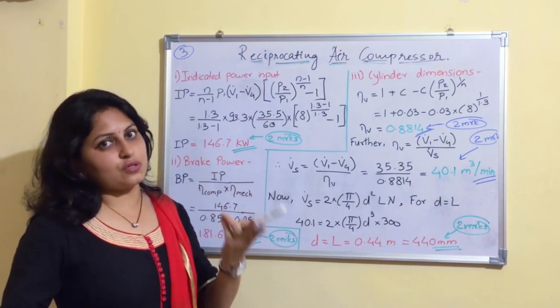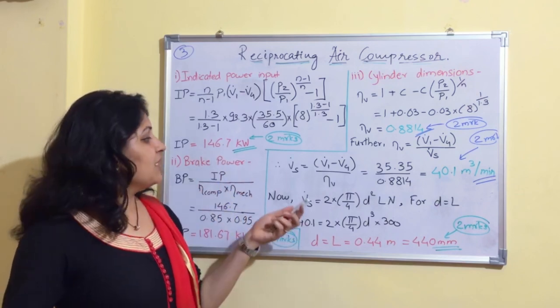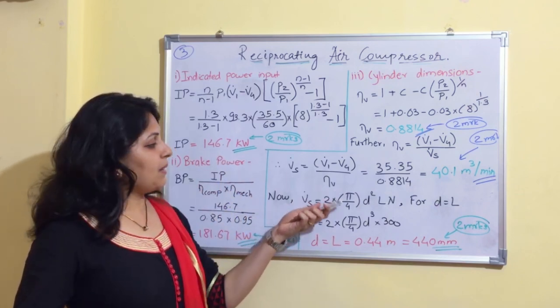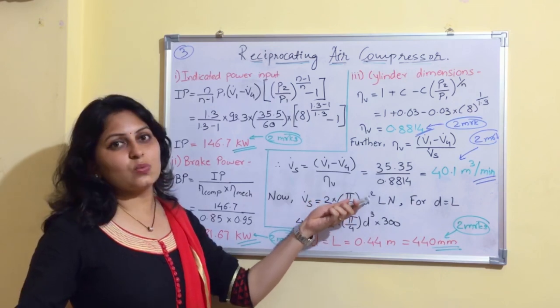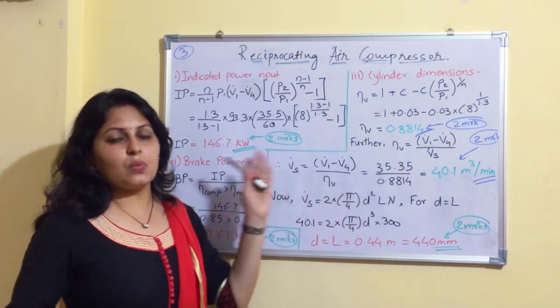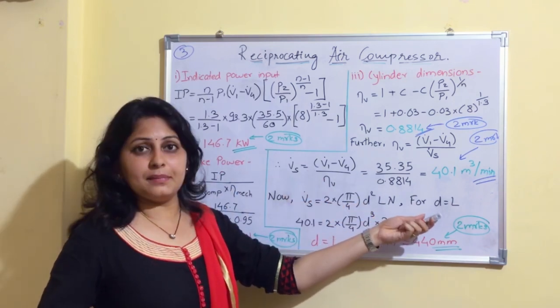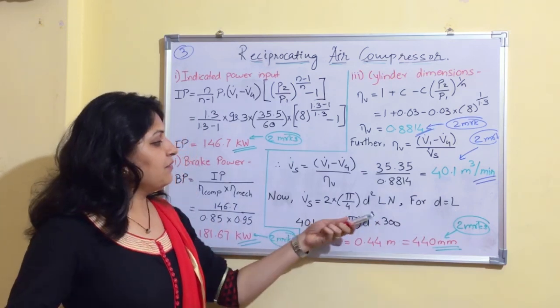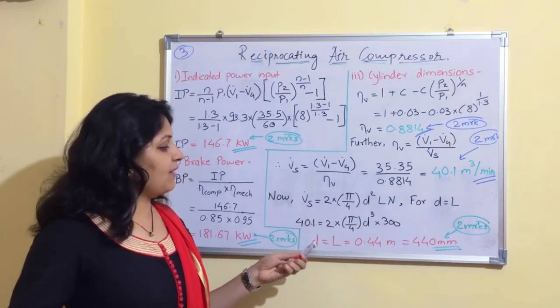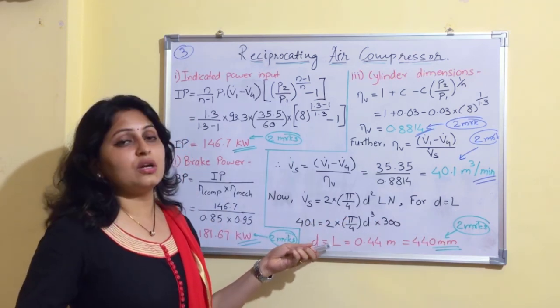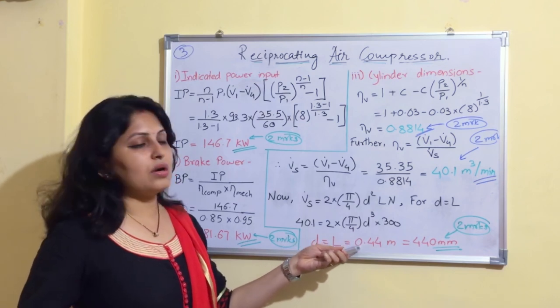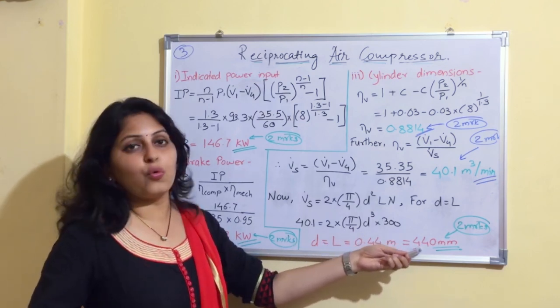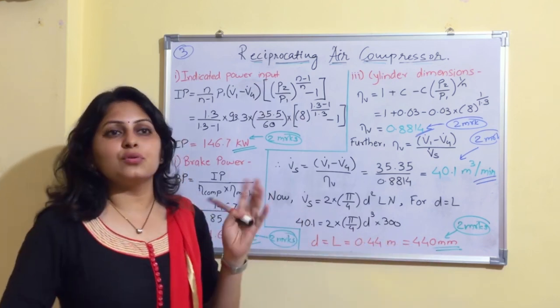Since there are two cylinders for single stage, the swept volume formula is Vs = 2 · (π/4) · D² · L · N. As given in the problem, diameter equals stroke (D = L). Substituting and solving, we get D = L = 0.44 m = 440 mm.